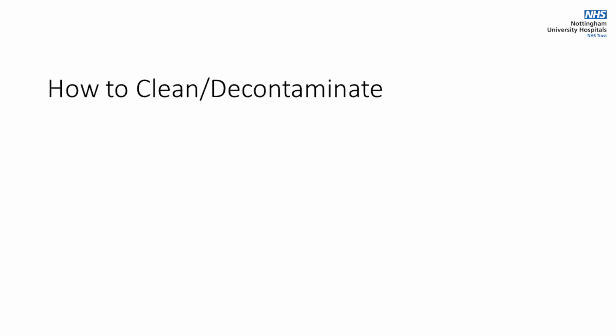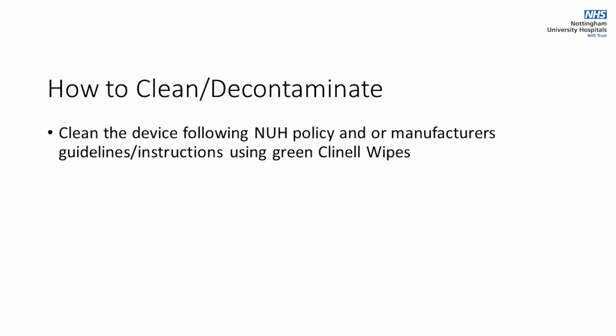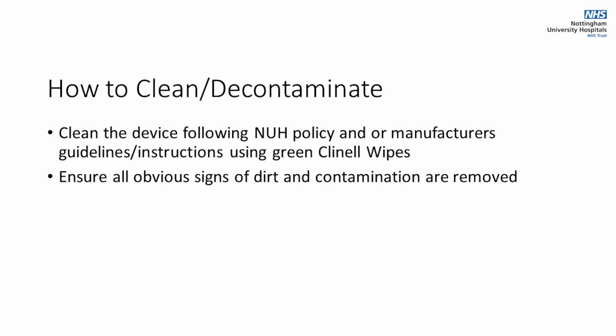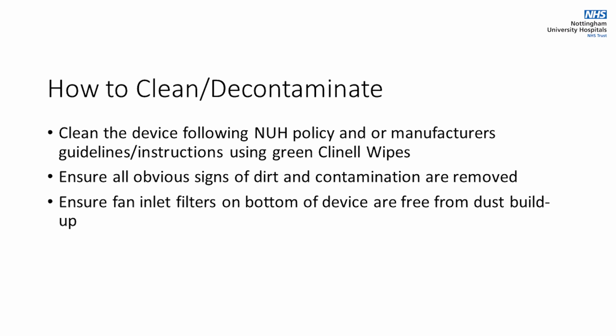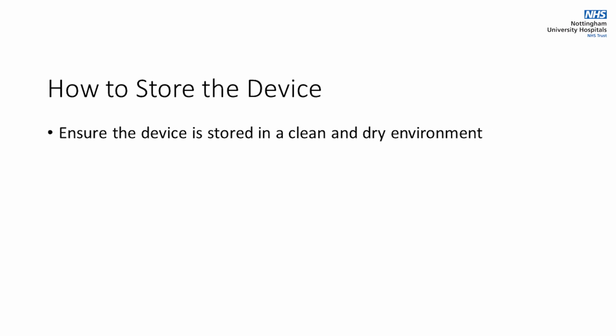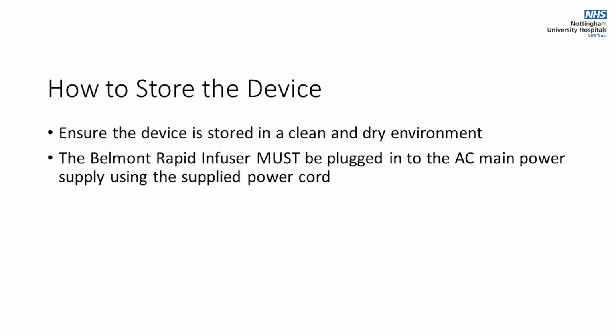How to clean and decontaminate the device. Clean the device following the NUH policy and the manufacturer's guidelines using green Clinell wipes, ensuring all obvious signs of dirt and contamination are removed. Ensure fan inlet filters at the bottom of the device are free from dust buildup. How to store the device safely. Ensure the device is stored in a clean and dry environment. The Belmont Rapid Infuser must be plugged into AC mains power supply using the supplied power cord. The power cord is specific to this device only.